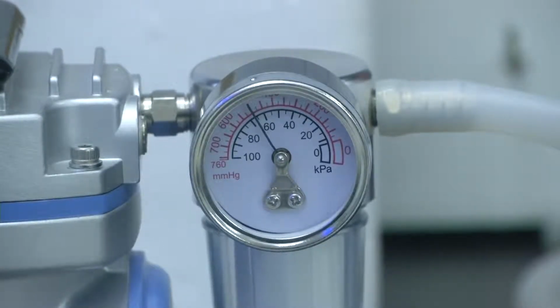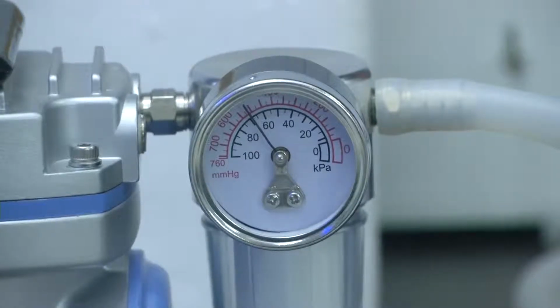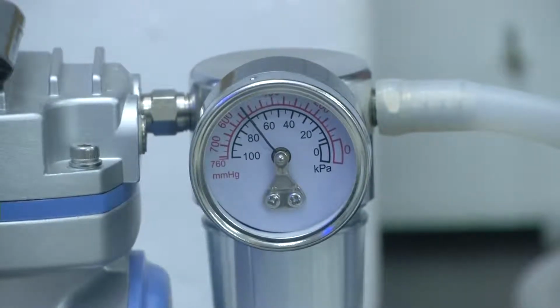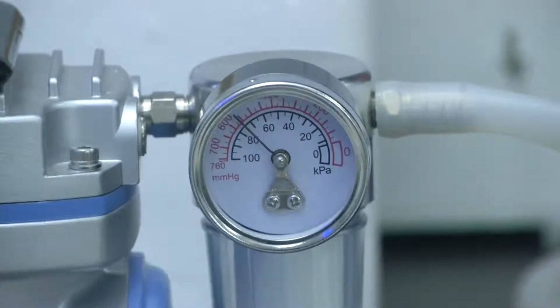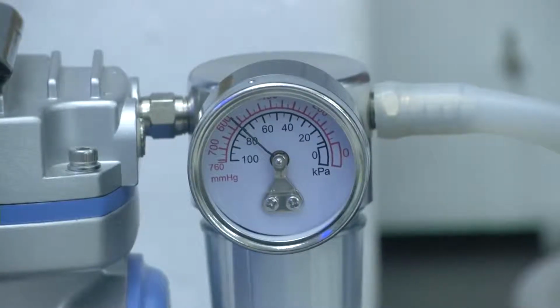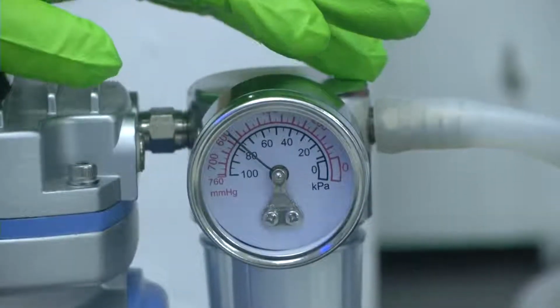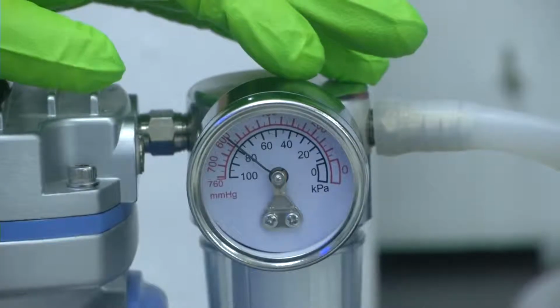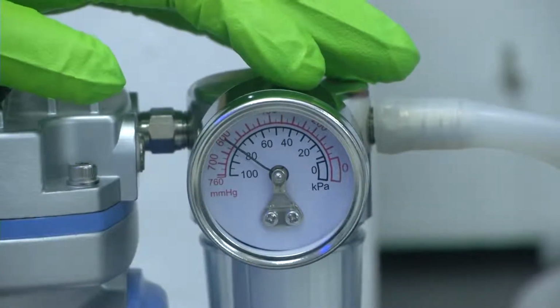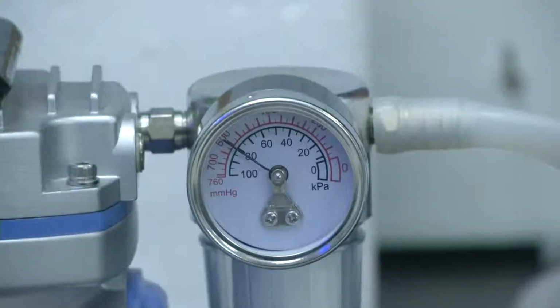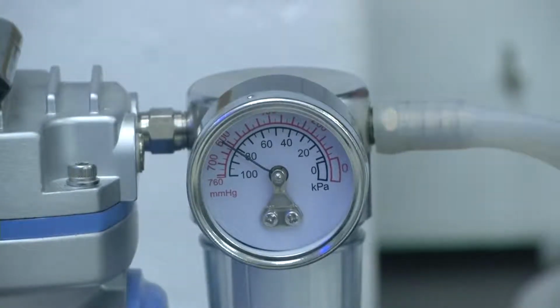That is because as vacuum slowly gets created, there is very little air that remains, and pulling this air becomes a little challenging process and it consumes a little time. Now it clearly shows that sufficient vacuum has been created, you can turn off the pump.